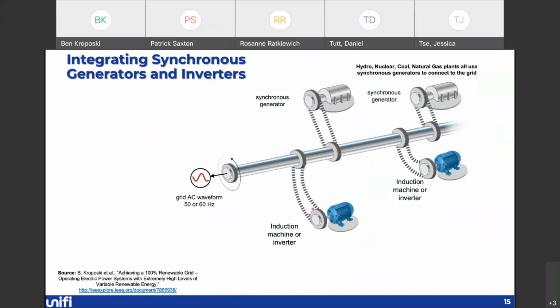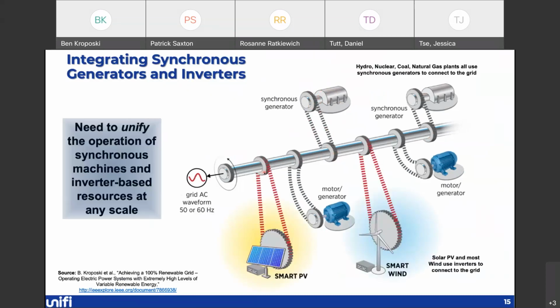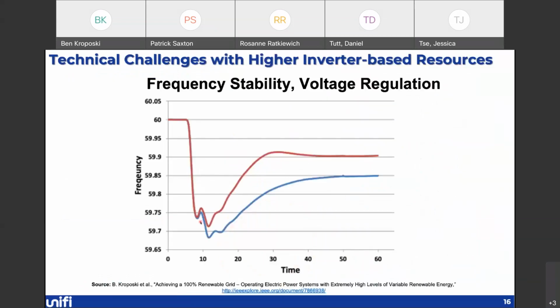allows the system to continually run. When we connect devices like induction machines or inverters, they don't have the same tight physical electromechanical coupling that synchronous generators do. But we're working on developing advanced controls for PV inverters, wind turbine inverters, battery inverters that actually mimic that response characteristic and are able to keep the system in synchronism even as we experience faults and the like. The key here is that we need to basically unify the operation of synchronous machines and inverter-based resources at any scale. So it could operate at 100% inverters, could operate at 100% synchronous machine, or anywhere in between. So here's some of the technical challenges.